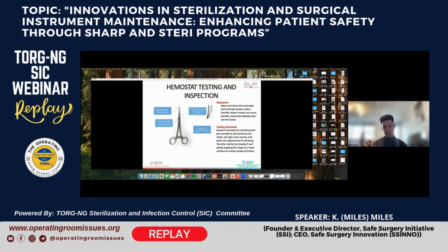So once you check that, you want to open the instrument up and look in the grooves. See if there's any kind of blood or dry blood or bioburden or tissue left over from the last patient or the last reprocessing. So you want to check in those grooves to make sure there's no bioburden inside of there as well. And then also going down, looking at the clamp area right here to make sure there are no cracks or anything like that.